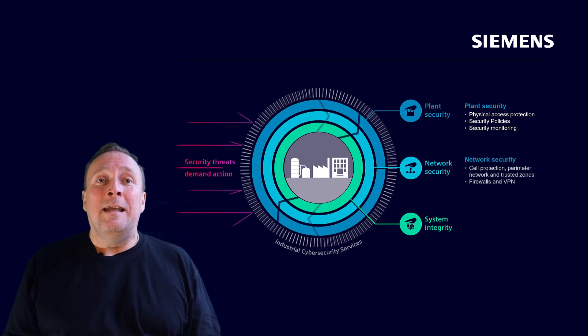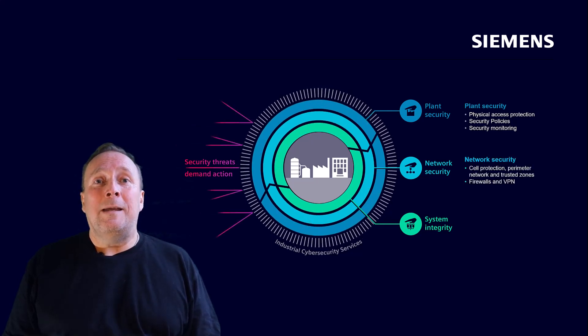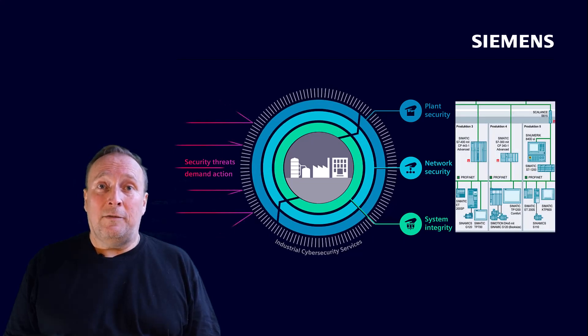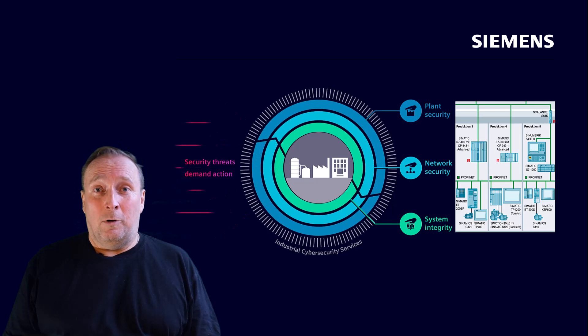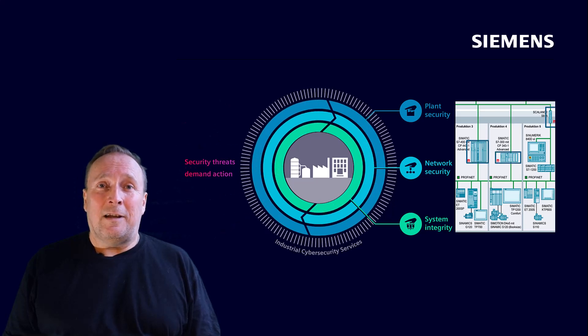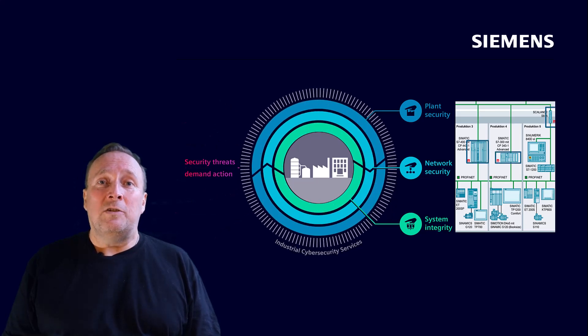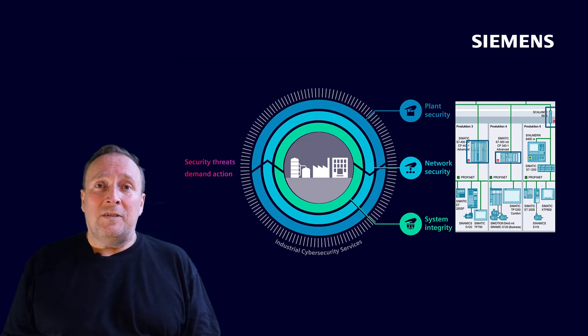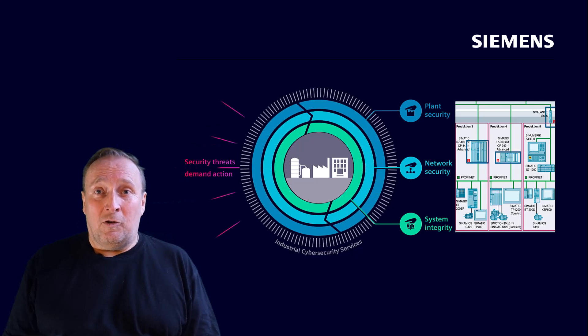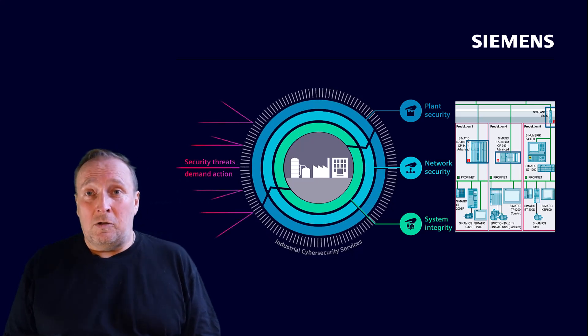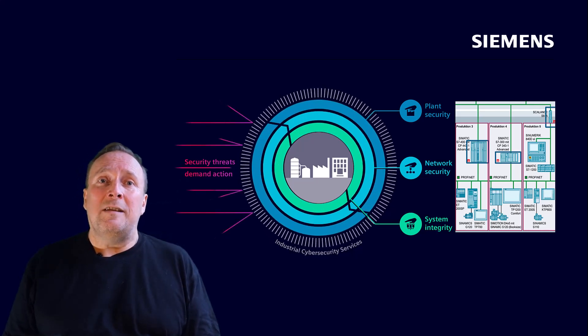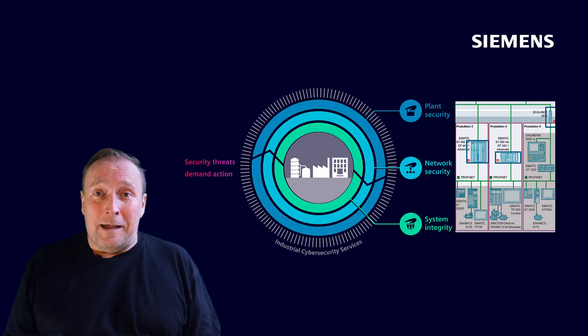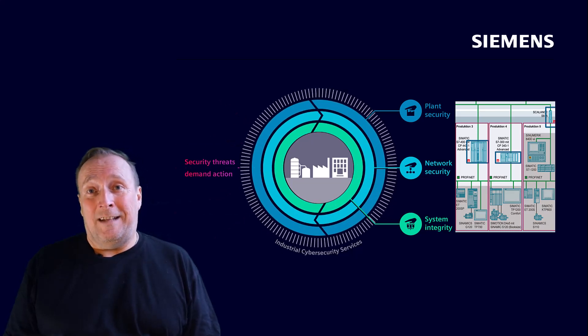Network security is implemented, for example, via cell protection. This means that individual secured cells are formed in a production network. These cells are protected by the use of special Scalance S or Simatic CP modules. Within such a cell, only the subordinate automation components — such as controllers, control panels, IOs, or Sinamics drives — communicate with each other, and are protected to the outside by the before-mentioned cell protectors.